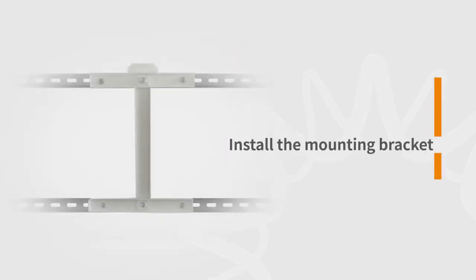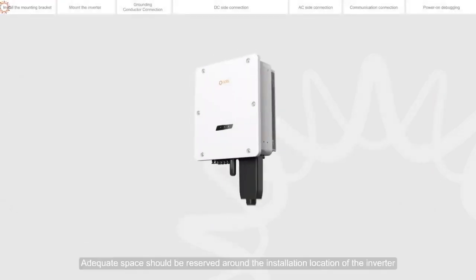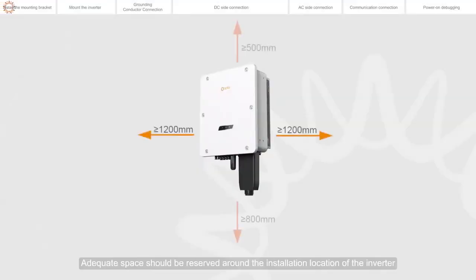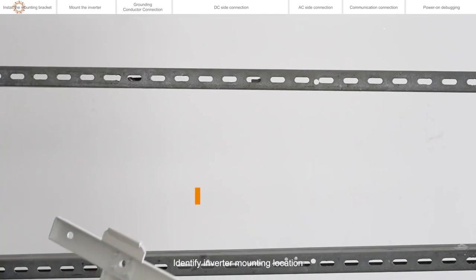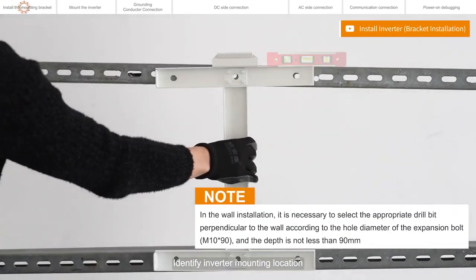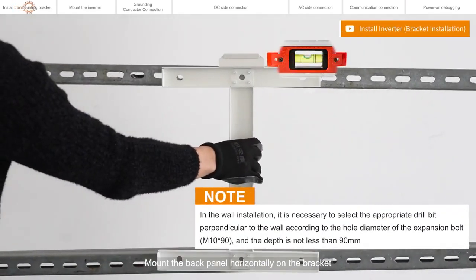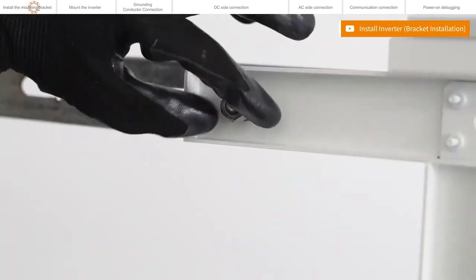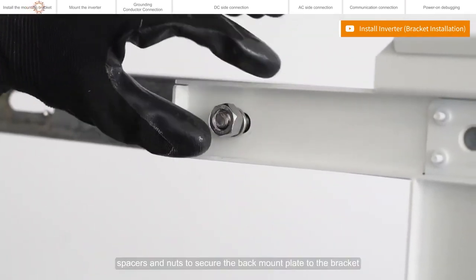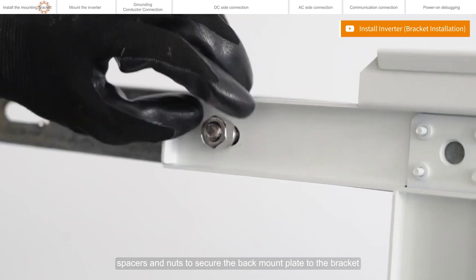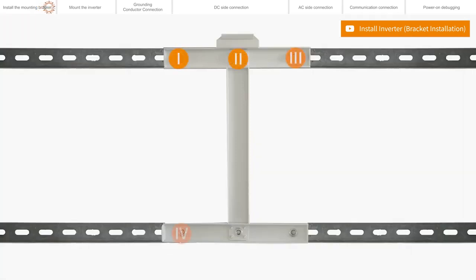Install the mounting bracket. Adequate space should be reserved around the installation location of the inverter. Identify inverter mounting location. Mount the back panel horizontally on the bracket. Use screws, spacers and nuts to secure the back mount plate to the bracket. Back panel installation completed.